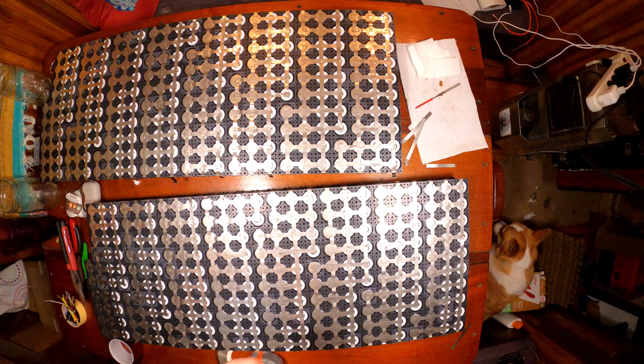In our case, our motor at full speed draws 400 amps. If we break that down into 5 banks that can each flow 80 amps, that becomes acceptable. That means the 5 banks in unison, all flowing 80 amps, will flow 400 amps to the motor. So everything in here has to be built to run 80 amps. If we were doing 4 banks instead of 5, we'd have to build each bank able to do 100 amps. That's how the system builds up.